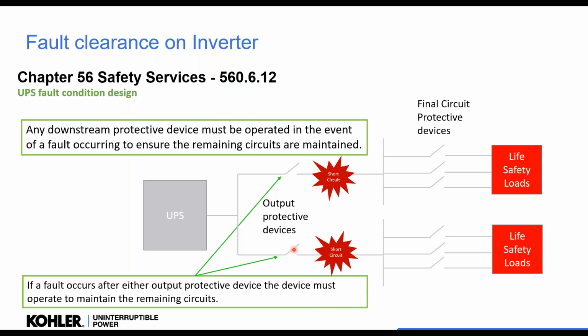Now, these sub-main breakers tend to take a lot longer to trip than MCBs. MCBs we could trip in 10 milliseconds. These could be 80 milliseconds or more to trip. Now, if you've got life safety systems or computers on it, there may be an interruption on those, because we are tripping that circuit breaker, which may take 80 milliseconds to trip, and that could cause an interruption. Something to be aware of. We might not want to mix loads on the UPS.